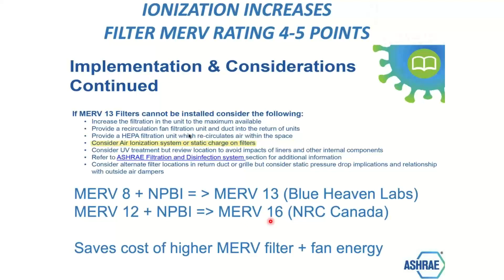In addition to ASHRAE and EPA, there's other folks that had some similar studies out there. These two labs, I don't know anything about those two labs. I just literally stole this slide from one of the ASHRAE guys because he referenced those two labs having tests. But they had a Merv 8 with a bipolar ionizer behaving like a Merv 13. A Merv 12 with a bipolar ionizer, in this other lab's test, behaved like a Merv 16. So you can essentially get a higher functional Merv rating out of your existing filter by combining it with a bipolar ionizer.